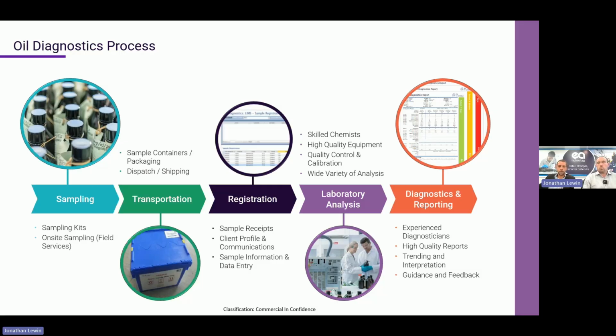One of the biggest issues we see as a lab, I'm sure it's industry-wide, is data transcription. Obviously the site guy goes to the asset, he reads that nameplate on there, serial numbers, manufacturer, some of those nameplates are very old, hard to read. That's then transcribed from the nameplate through to the sample label. From there, that's sent to the laboratory, where the registrar reads that information, registers into the system. Any point there could be a transcription error. Is that a 5? Is it an S on the serial number? And other issues can arise. How we propose to address that is something that we'll come on to later in this presentation.